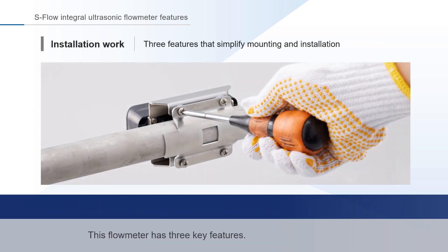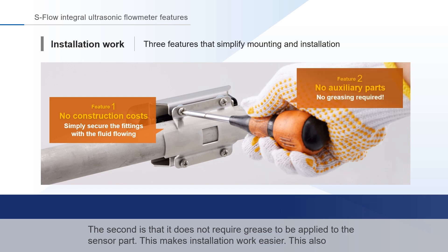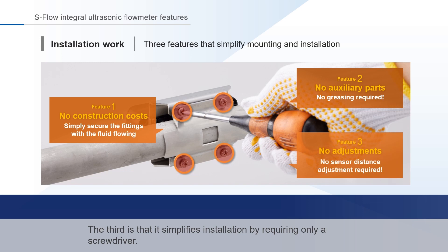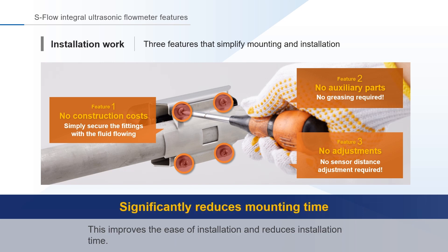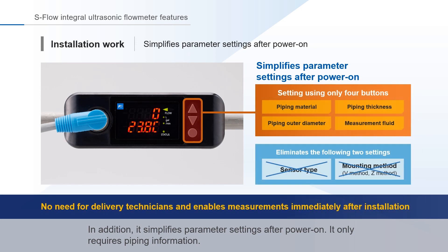This flow meter has three key features. The first is its clamp-on system — it eliminates piping work and can be installed while the fluid is still flowing. The second is that it does not require grease to be applied to the sensor part, which makes installation easier and eliminates the risk of grease contamination. Therefore, it can be used in environments where strict sanitation control is required. The third is that it simplifies installation by requiring only a screwdriver. These features make it easy to install the ultrasonic flow meter even for inexperienced workers, improving ease of installation and reducing installation time. In addition, it simplifies parameter settings after power on, requiring only piping information.